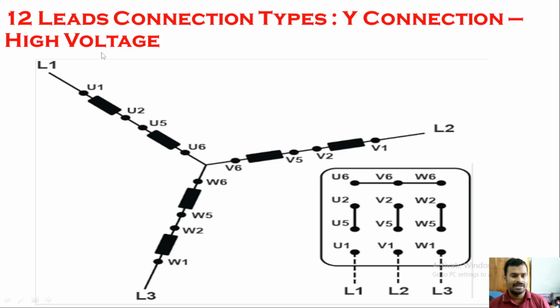So in here it is a high voltage configuration. So L1 will be connected to U1, L2 will be connected to V1, L3 will be connected to W1, and U2 U5 shorted, V2 V5 shorted, W2 and W5 shorted, and these three, U6 V6 W6, will be shorted as well. If you connect this way, it will act as a star connection high voltage configuration.